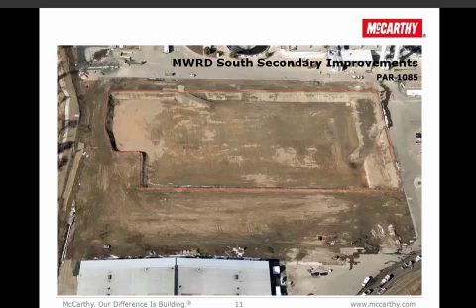The key here is that during this phase of the project, we need to start looking at how we are going to be testing and starting up this plant. Prior to installing any concrete during the design phase, we can determine if it's necessary, instead of having a plain end wall casting, to have a flanged wall casting that will allow us to add recirculation piping. In addition, we may be able to add a couple of valves that will allow us to recirculate piping, which will help us manage the use of water and startup of equipment prior to going into the actual process treatment.